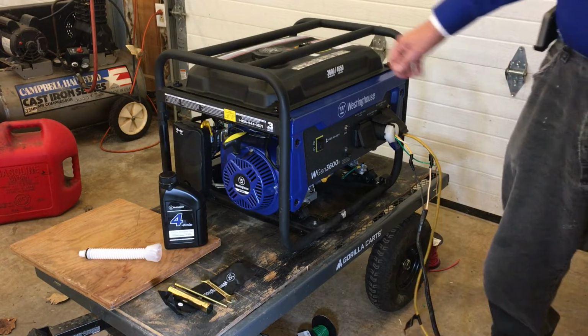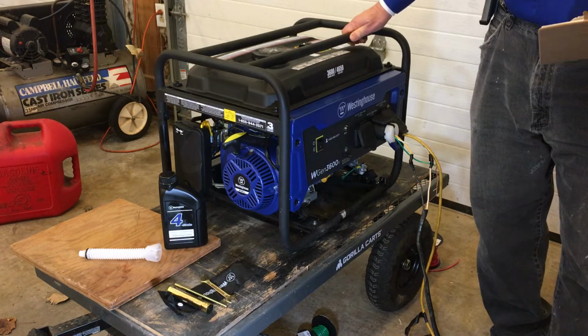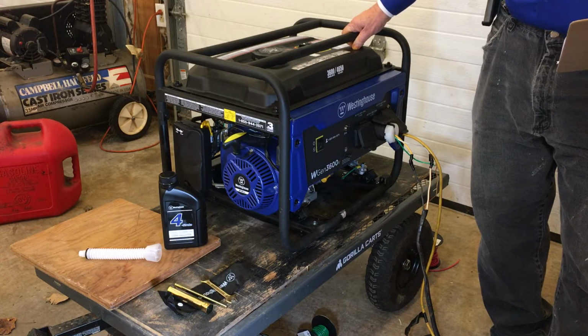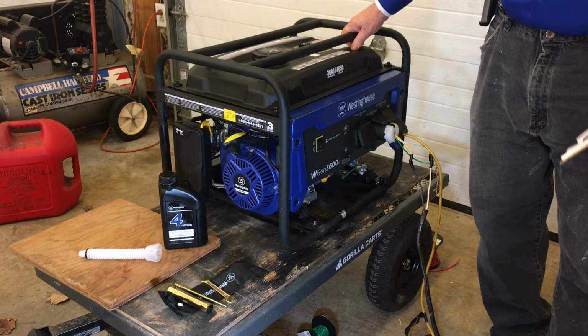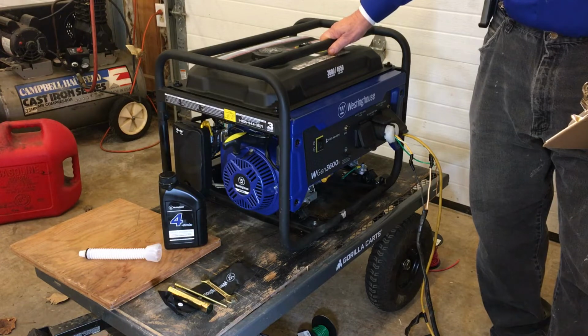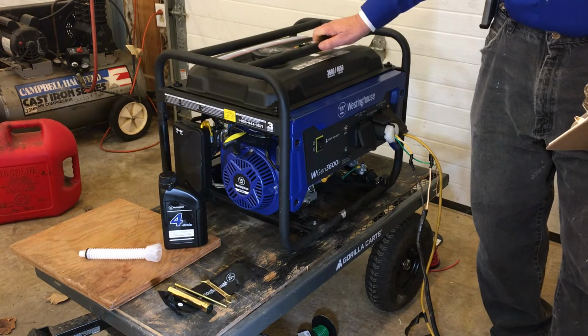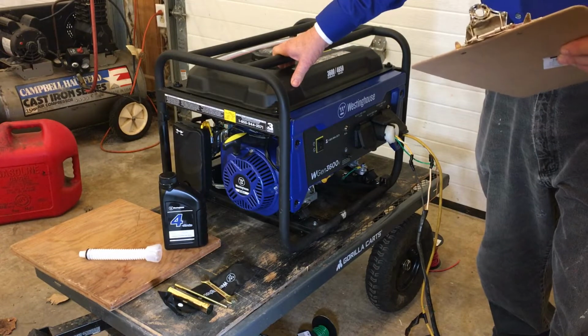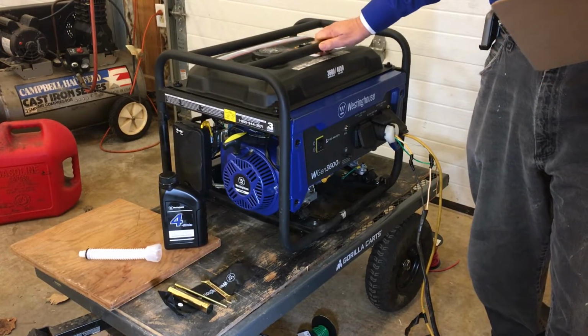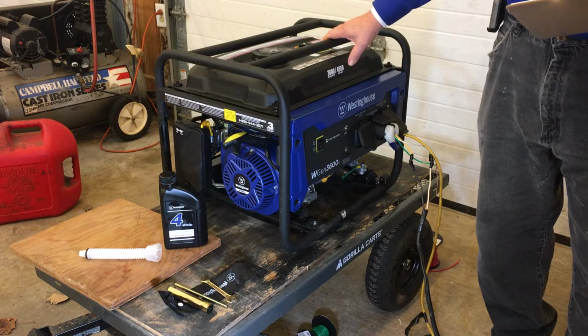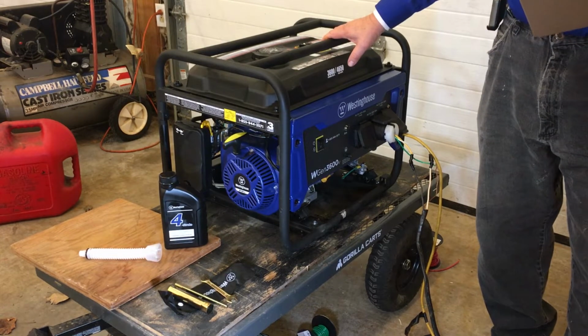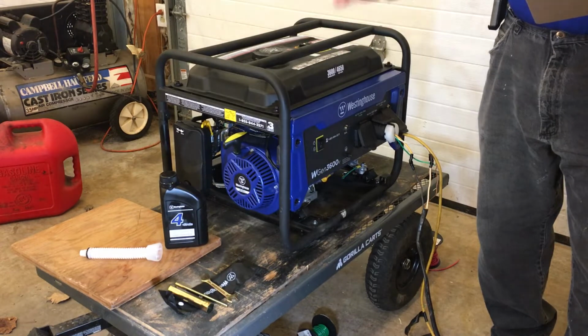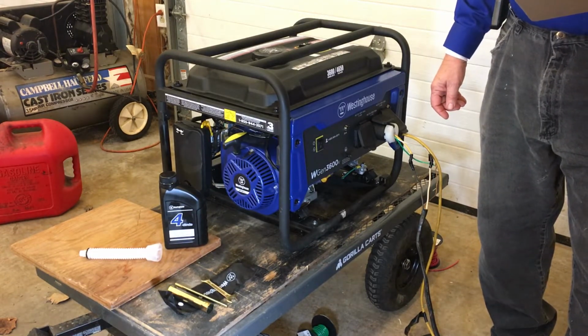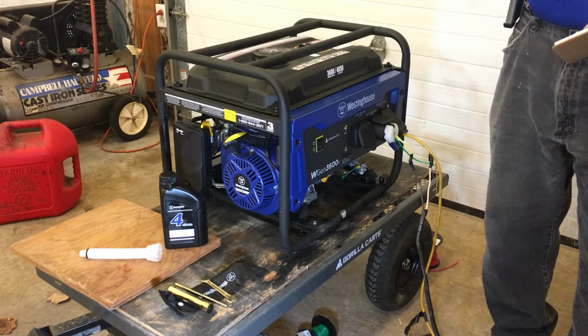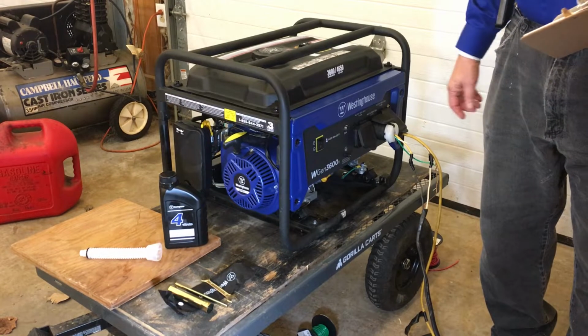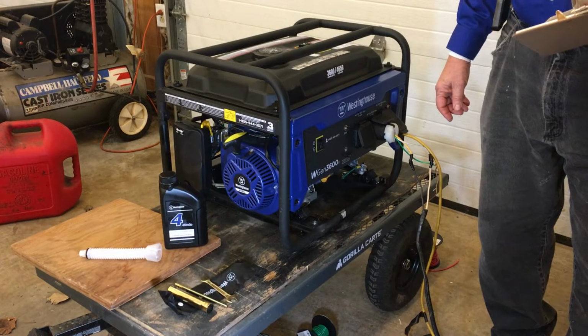Hi folks, today we're going to do a load test on this new 3600 watt rated generator. The reason for the test is basically to see if it meets the manufacturer's claimed rating. Because of the noise of the generator and also a cooling fan on our load bank, which we'll discuss in a minute, we're going to provide an audio narrative of the process and then insert clips into that of the actual test that has already been completed.